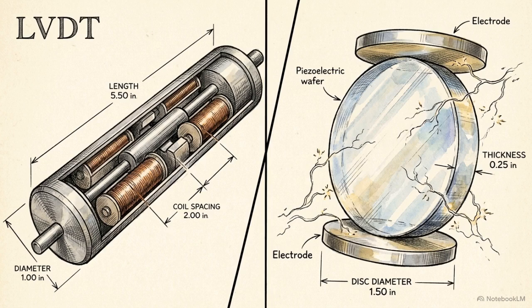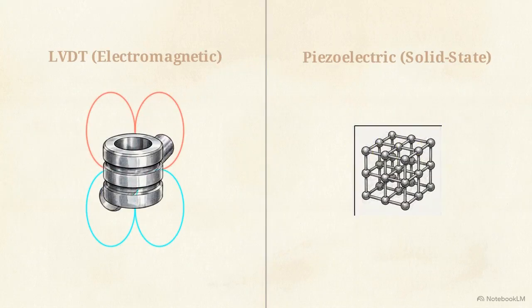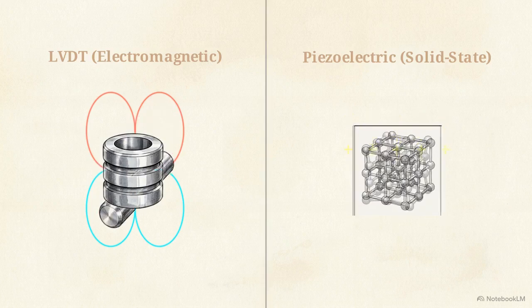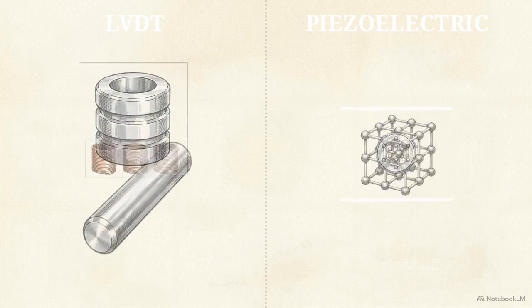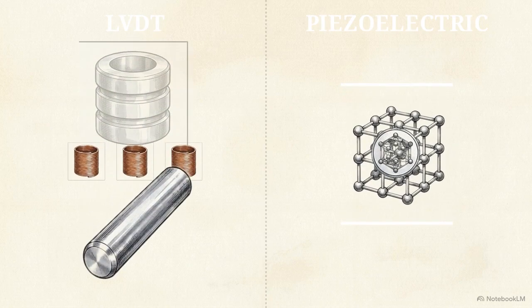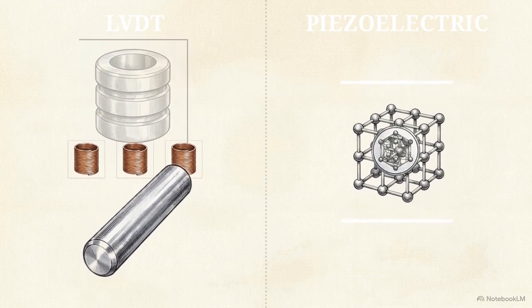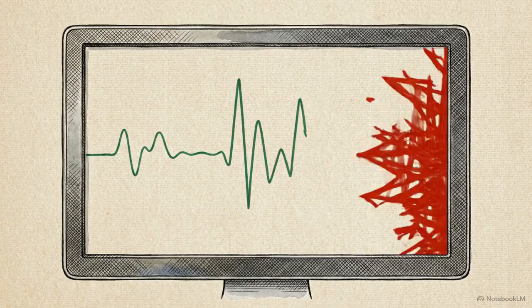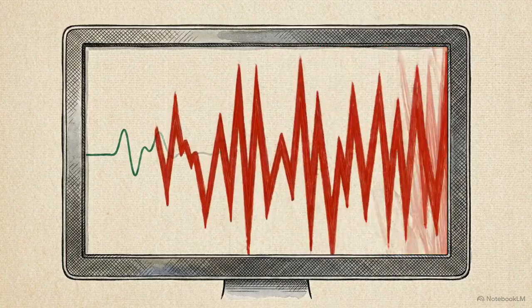For hyper-fast, solid-state measurement, the standard is the piezoelectric transducer. One device utilizes magnetic fields and internal geometry, while the other utilizes molecular distortion within the material itself. Selecting the correct sensor depends on understanding the foundational physics driving each device. We will deconstruct their internal architectures, trace their working principles, and identify their physical limitations. Relying on the wrong physical mechanism for a specific measurement regime leads to a complete failure of the data.